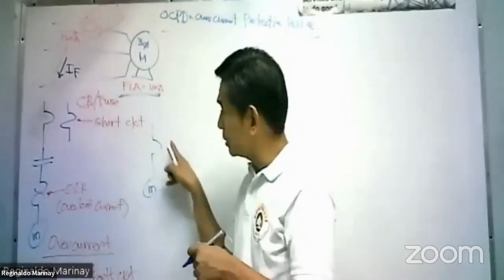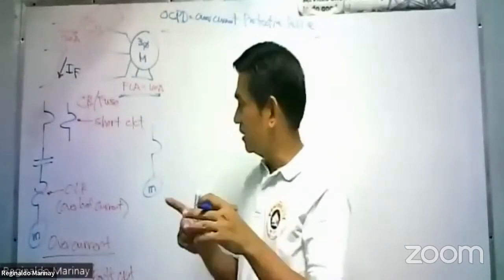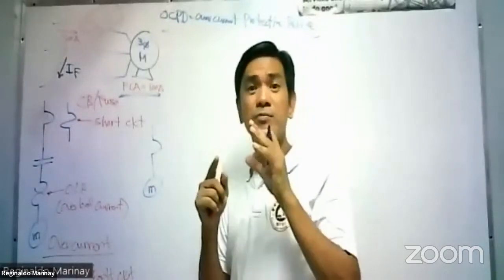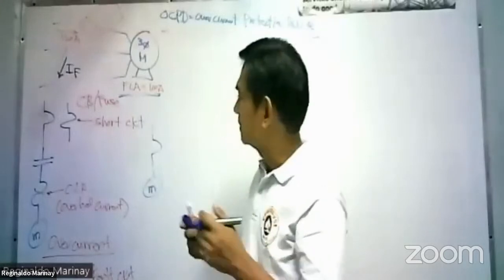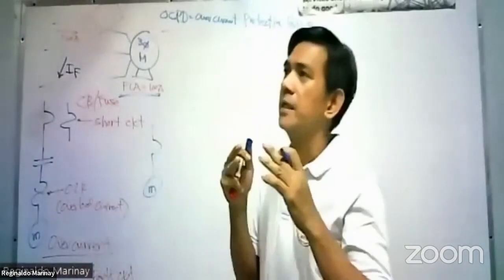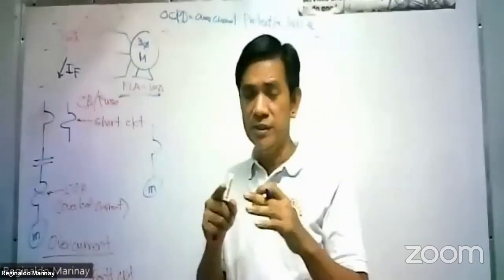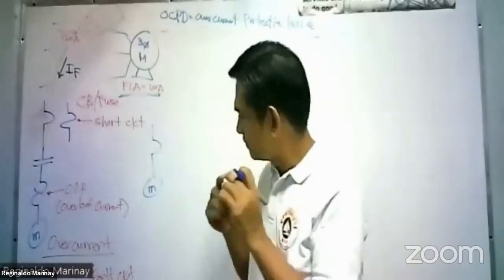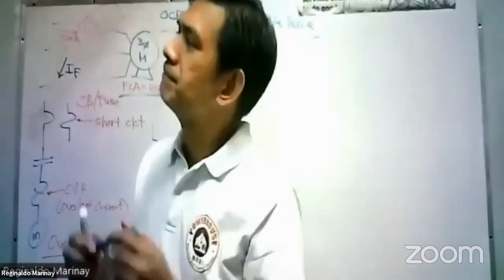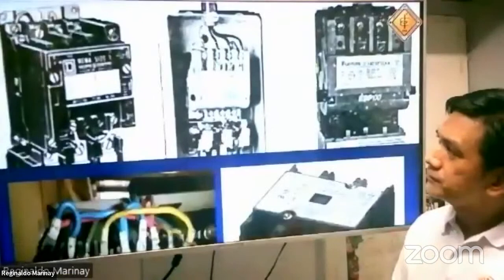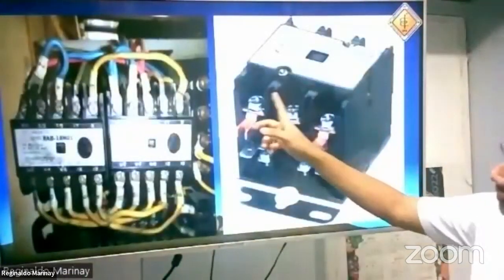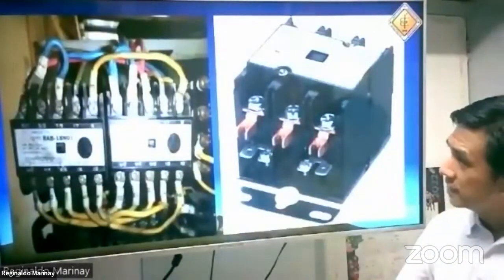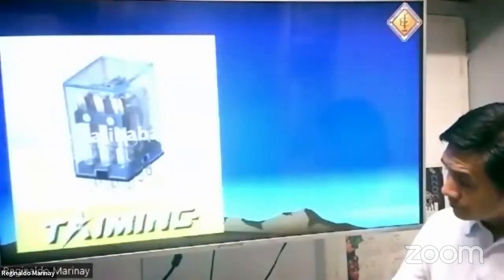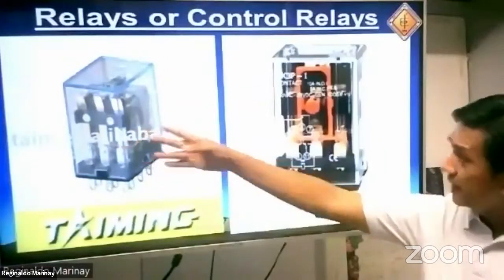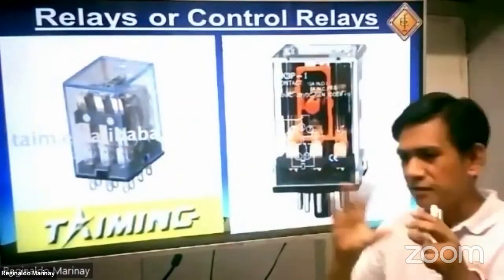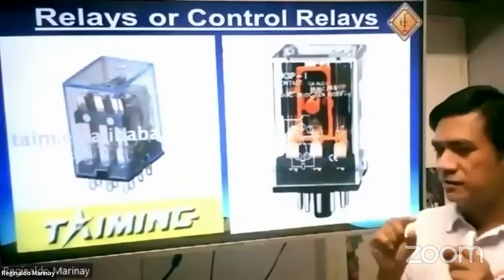Aside from being a short circuit protection, nowadays the technologies of circuit breaker already have an overload protection element or device inside. So this circuit breaker has the capability to trip even though there is no short circuit; even if it is just an overload current, it may trip. Okay, so there we have, this is a magnetic contactor. See here, that is a magnetic contactor. Then we have an overload, there is a relay or control relay here. This is for a smaller capacity or current of the relay.